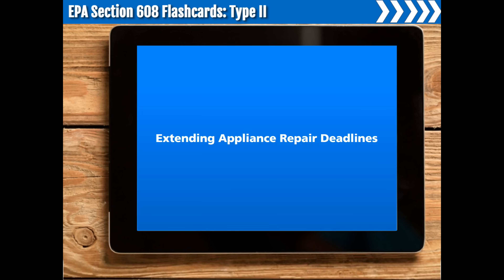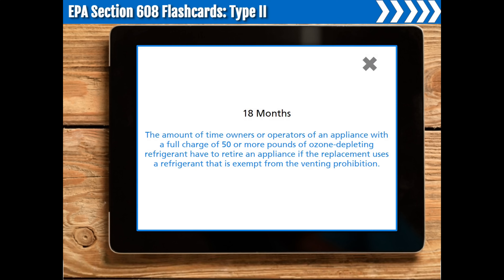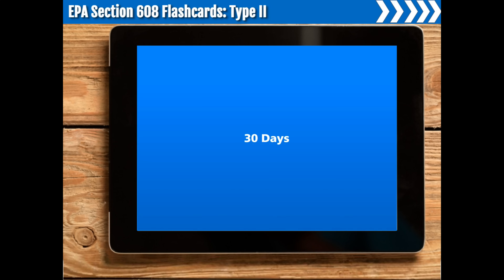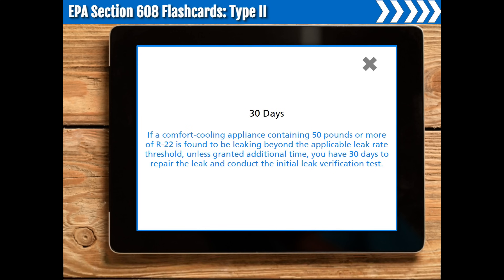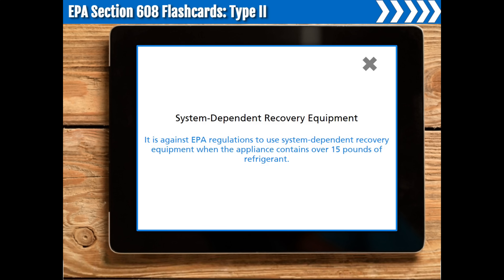Extending appliance repair deadlines. A certified service technician not being available cannot be used as a reason to extend the appliance repair deadlines. 18 months. 18 months is the amount of time owners or operators of an appliance with a full charge of 50 or more pounds of ozone-depleting refrigerant have to retire an appliance if the replacement uses a refrigerant that is exempt from the venting prohibition. 30 days. If a comfort cooling appliance containing 50 pounds or more of R-22 is found to be leaking beyond the applicable leak rate threshold, unless granted additional time, you have 30 days to repair the leak and conduct the initial leak verification test. System-dependent recovery equipment. It is against EPA regulations to use system-dependent recovery equipment when the appliance contains over 15 pounds of refrigerant.